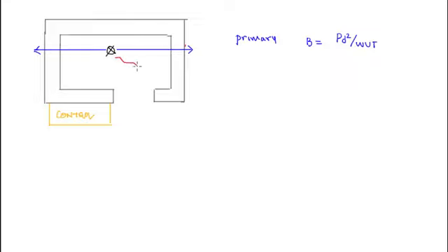But there are other kinds of radiation too. There's leakage. That's leakage through the head of the linac and coming through the walls. Okay? And it comes in all directions through the barriers. And the formula is very similar. So the design goal P, the distance, and the use factors.